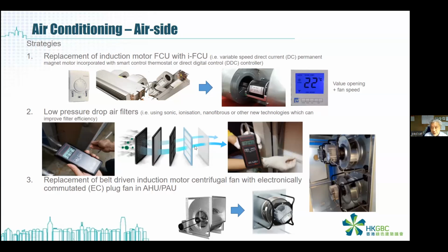This is the new filters. So the pressure drop is not hundreds, it's only 17. We use the low pressure drop one, which gives only around one third to 40% savings in the pressure drop. This is very significant. When you put it into the systems, you can reduce the air fan pressure head requirement.